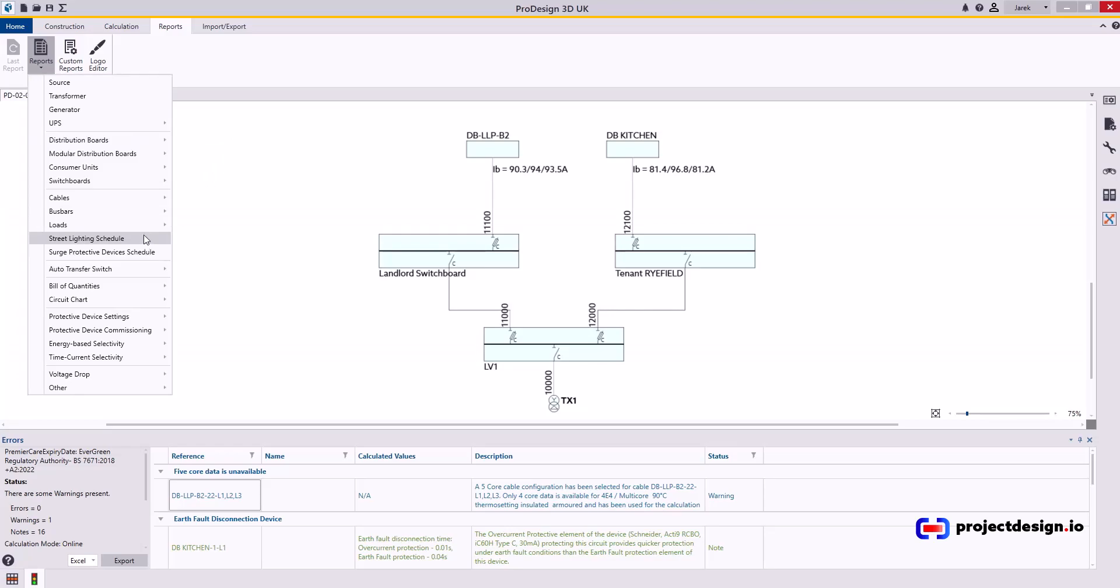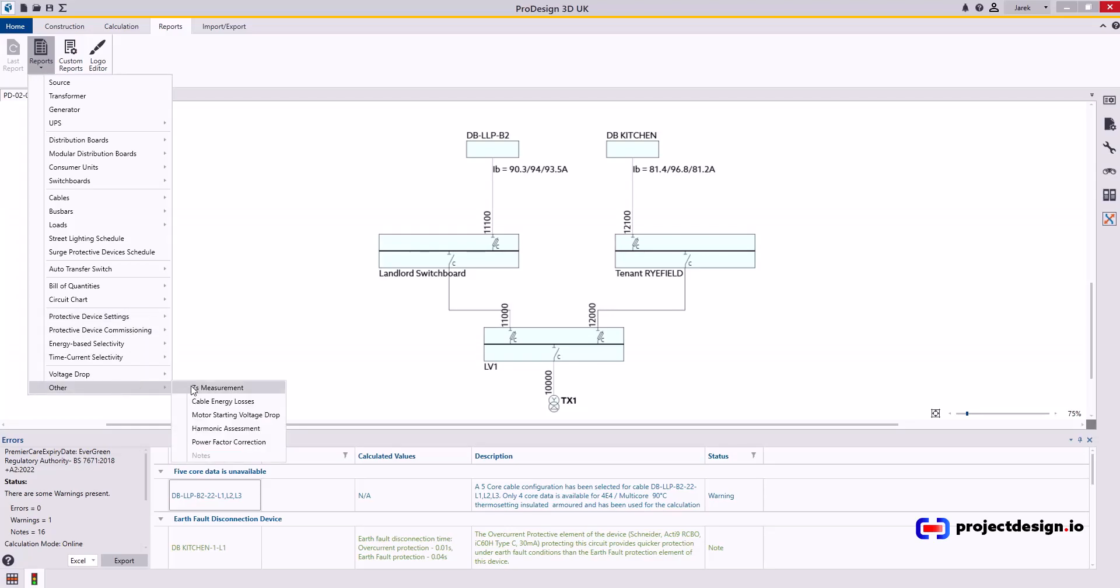And also protective device settings report is very useful especially towards the end at the commissioning stage. It's actually critical information. And sometimes it's very useful to print this ZS measurement report to confirm your design calculations during testing.